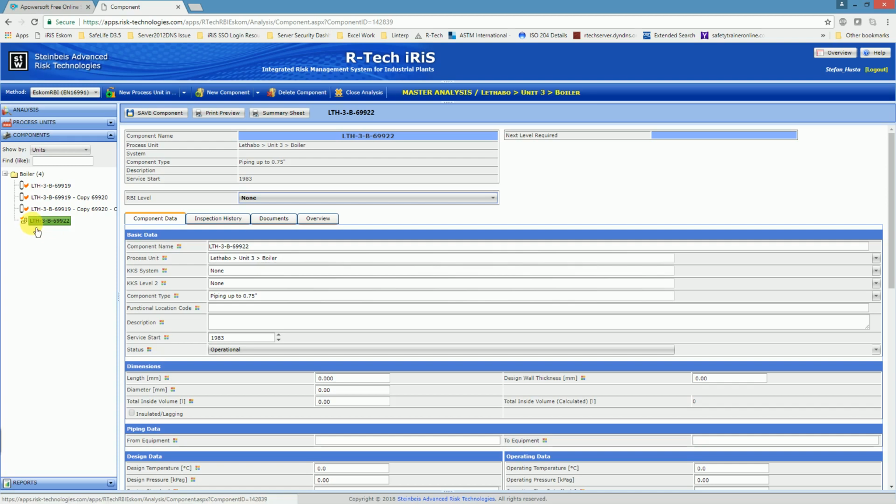It takes basically the first letter of the component, the power station. It takes the next two consonants. It takes the unit. It takes the plant area, B for boiler, T for turbine, G for Generator, and C for common plant. And then it takes something which is called the component ID within the database, which is completely unique for every single component in there.